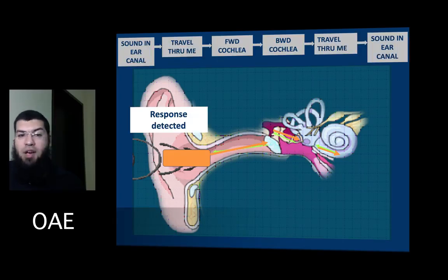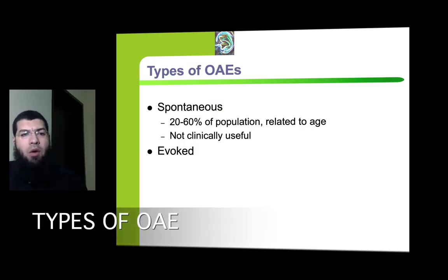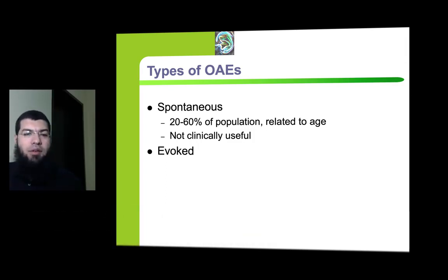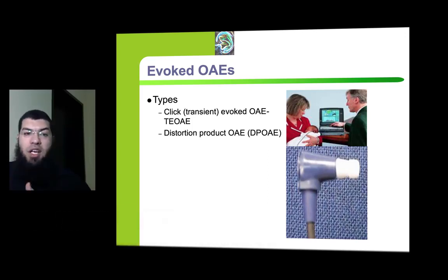Let's move on to otoacoustic emission. This is a model of how the otoacoustic emission device works. The sound is delivered to the ear canal, through the middle ear into the cochlea, and returns from the cochlea to the middle ear to be detected in the outer ear with a highly sensitive microphone in the probe of the otoacoustic emission device. We have two main groups of otoacoustic emission: spontaneous, which has no clinical significance, and evoked.